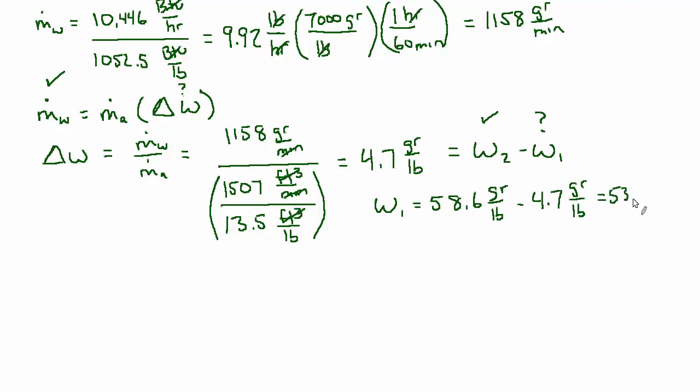So what are we saying? We're saying that the entering air has this humidity ratio, 53.9, then it acquires an additional 4.7 in the space, which is resulting from the latent load, and then it ends up at 58.6 as the leaving condition. That's omega 2. So if that sounds believable, we now know two things about the entering air.